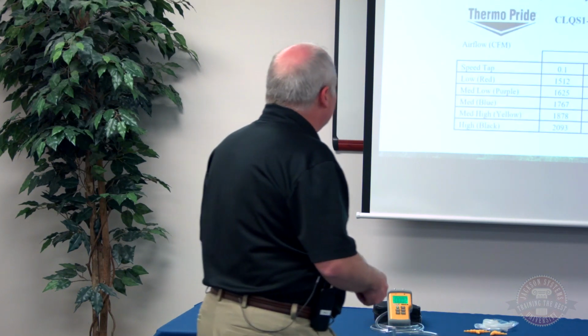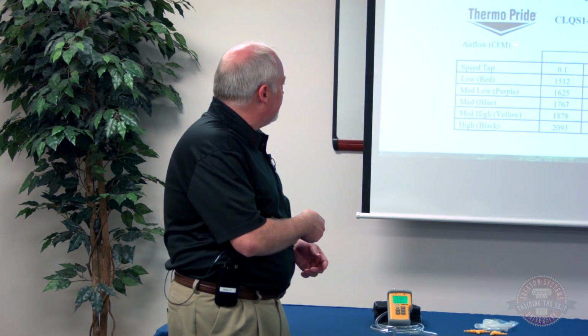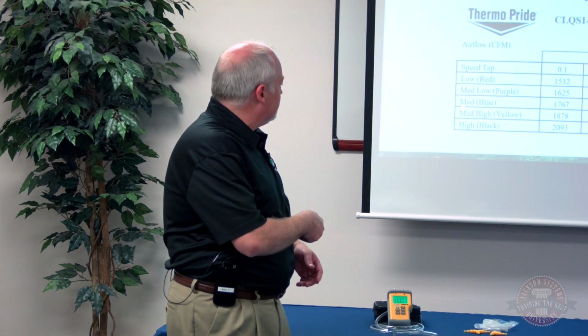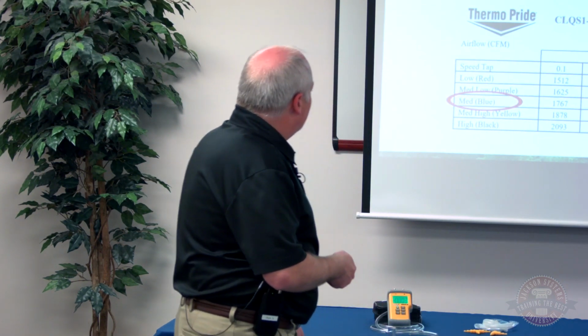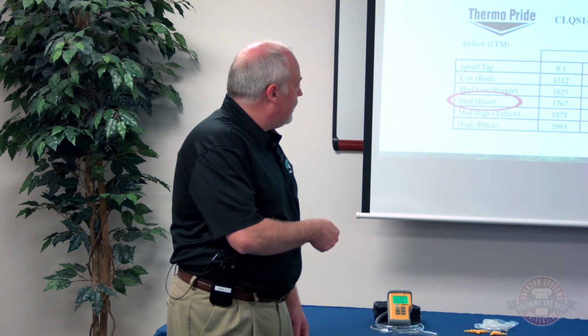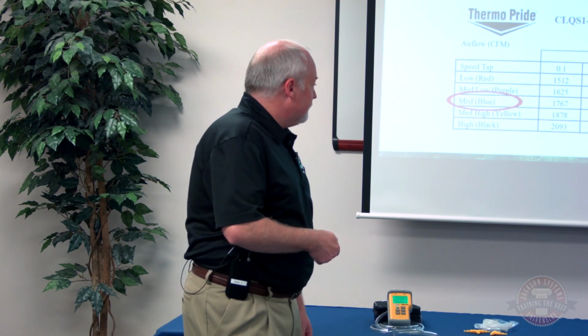How can we use that in a real situation? Typically, with the equipment that you're installing, in this case I used a Thermopride, their new 95% gas furnace as an example. This is our CLQS1. It's got an ECM constant torque motor. So this chart shows us at which speed tap, at what external static pressure, the CFM that piece of equipment is moving. So in this case, let's take a look at the 75,000 BTU furnace with a 1/2 inch of external static pressure. On medium speed, it is going to move 1,513 CFM of air through that duct system. Okay?